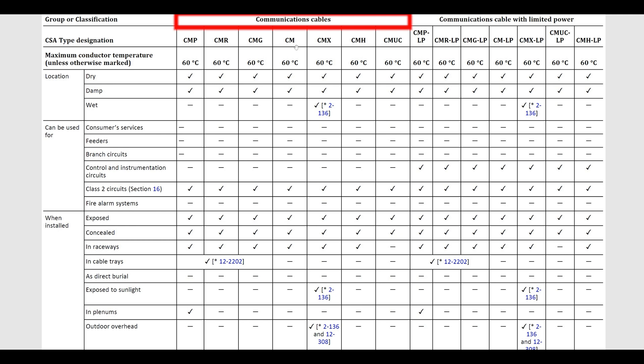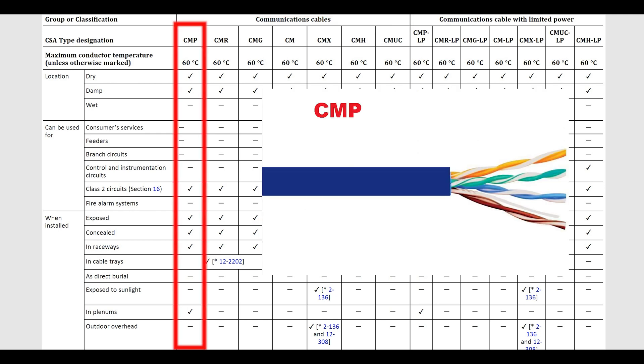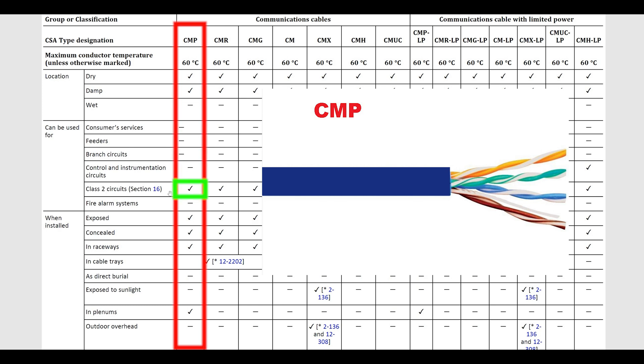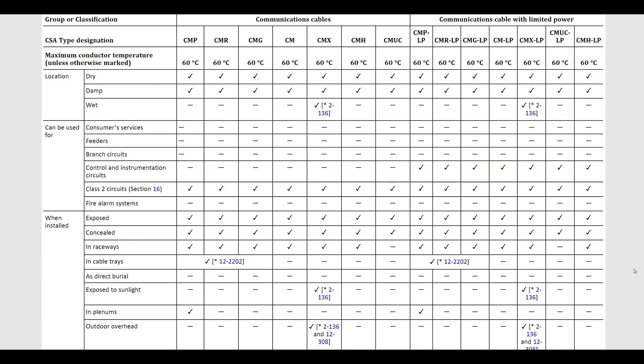Some of these are very similar to each other. Just to pick one at random, CMP cables—pretty common. I'm sure you've seen this before. It's pretty delicate stuff, it's not good for most applications. Definitely can't be wet. Obviously you're not using communication cables for feeders or consumer services or branch circuits, but it is good for class two, in raceways is good, exposed, concealed, and in plenums as well. That's free air in the plenum space is allowed.